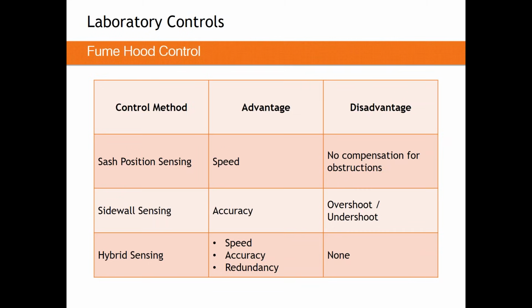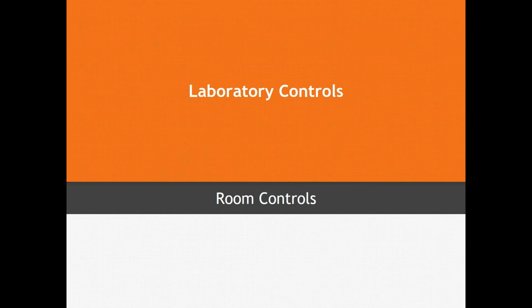Hybrid sensing is the most preferred for all of these fume hood technologies because it is the fastest and most accurate system we can offer. Now, before we open the floor up to questions and before we close out for today, I want to introduce room controls. Antec Controls by Price is a controls manufacturer. The valves are a medium for the controls, but oddly, what we talk about most are the Venturi valves. But the whole entire point of this presentation leads up to how we control and pressurize a space.